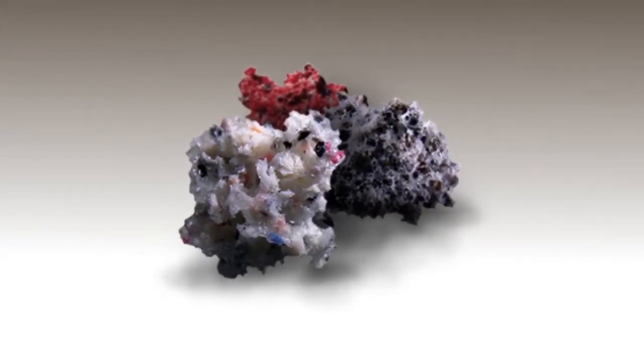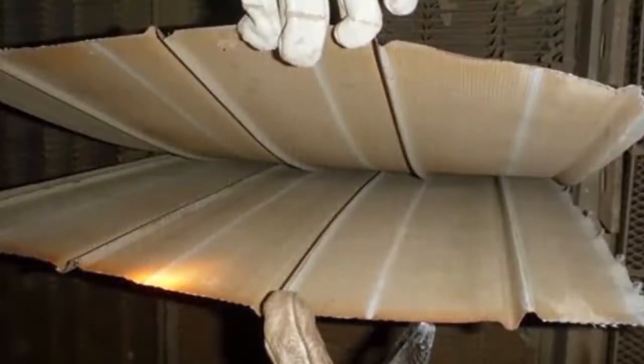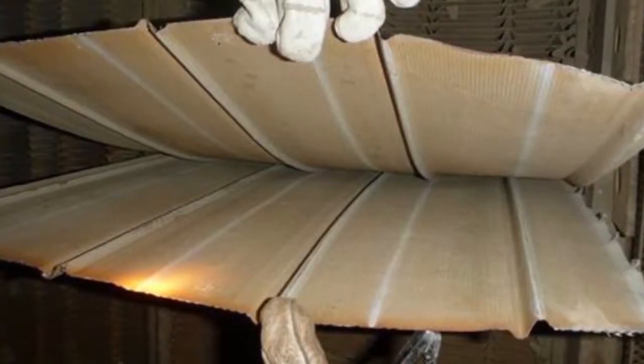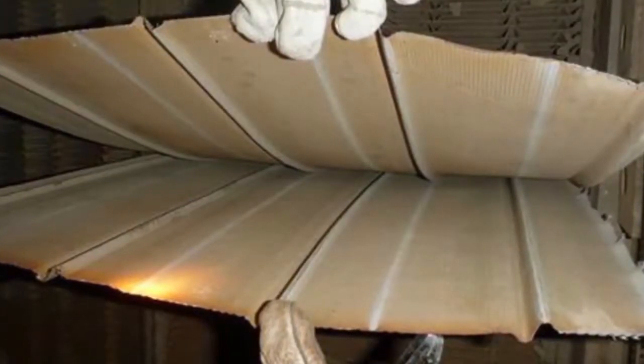In addition, Thompson provides a pneumatic thrusting of all modules as a final touch to ensure overall maximum effectiveness. As seen in traditional catalyst cleaning processes, simply vacuuming the top of the screens and possibly air lancing is not enough. After removing the screens, Thompson utilizes proprietary encapsulation ash recovery equipment, ensuring removal of entrained ash dislodged with our specialized vibration method. Thompson can clear the innermost catalyst ash.